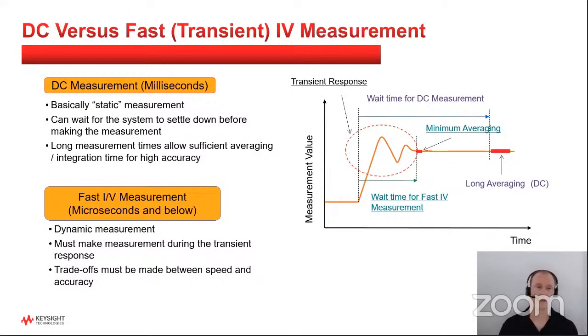When you go from making DC measurements or even pulse measurements with an SMU to making what I would call fast transient IV measurements, there typically are some trade-offs you have to think about. If you look at that graph in the upper right there, it shows the difference between trying to make maybe a fast pulse measurement and an SMU or long averaging type measurement. And again, when you're making SMU measurements, we generally assume that we can have as long a wait time as we want, or hold time, to stabilize everything out before we make the measurement. We oftentimes don't have that luxury in a fast pulse measurement, because we're trying to pulse very quickly, so sometimes our equipment doesn't stabilize all that fast. So you may have to make some trade-offs.